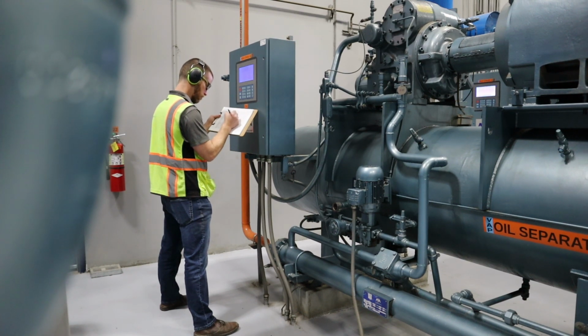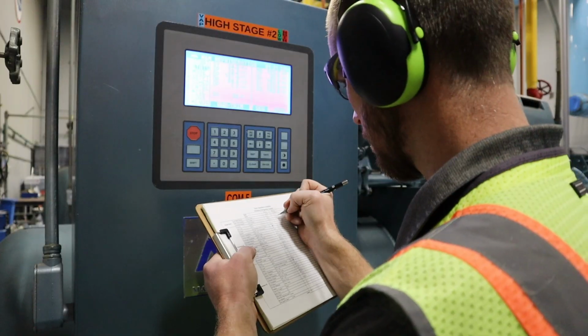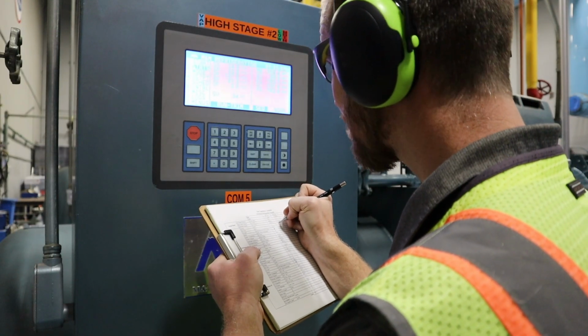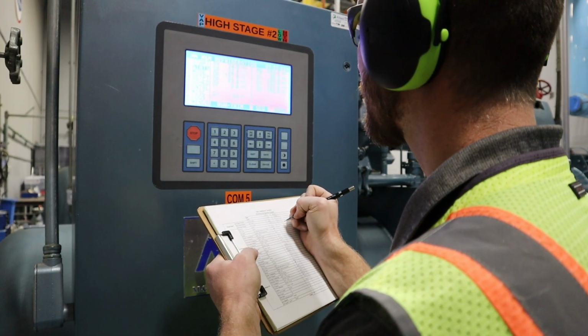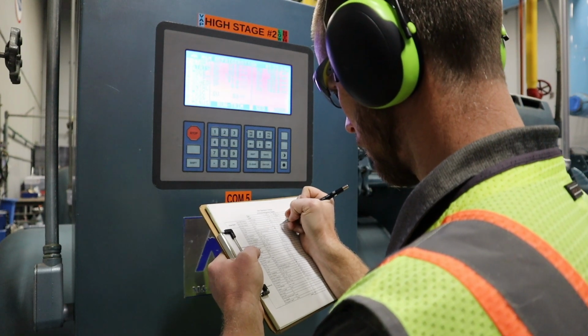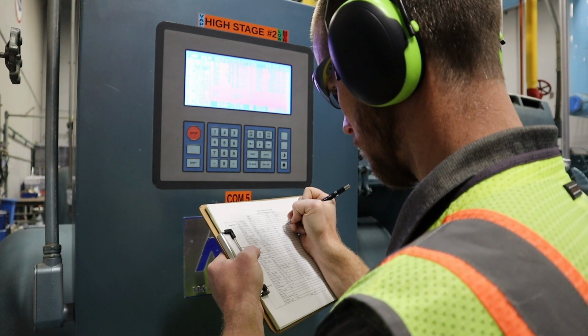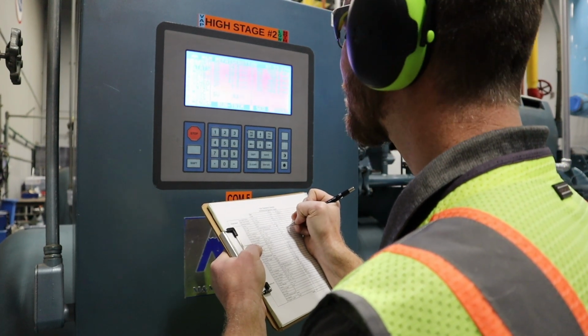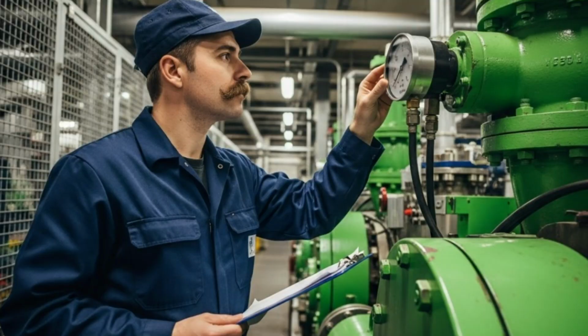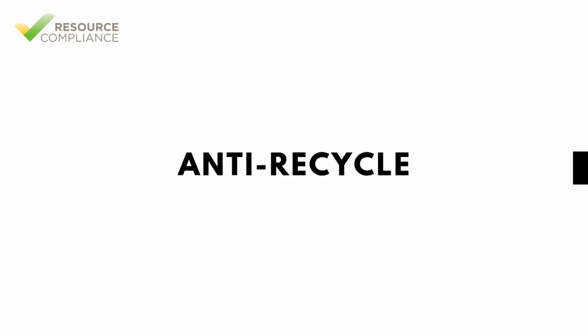Many compressors can be started in auto or local modes. Auto means the compressor will be started and stopped automatically based on algorithms in the control system. In local, the compressor will be started and stopped by the operator using the switch on the compressor panel. After starting a compressor, the operator must monitor it closely to ensure it operates safely within the operating limits of the system. Screw compressors are typically protected from short cycling by an anti-recycle timer.